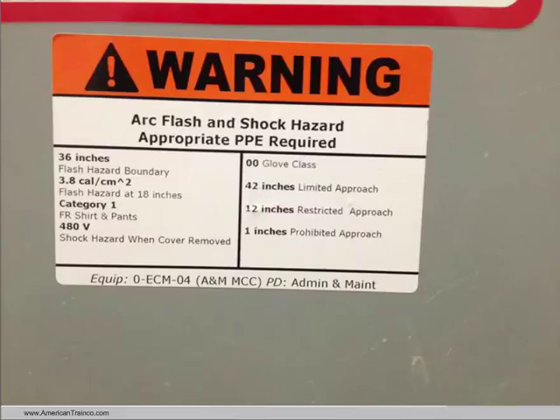So let me give you an example of where that might be a little bit of a conflict. We do the incident energy analysis method. Great. We put on the label the number of calories. Let's say it's 8.3 calories. Okay, I can go out and buy a long sleeve arc-rated shirt that would take care of 8.3 calories. It could be rated at 10.1 calories. Same with my long pants. I could get 10.1 calorie rated pants. But when that label says 8.3 calories, if I used the table method, and if we put category 3 on there, which would be the equivalent table method, my shirt and pants don't cut it anymore. I have to have a full-blown flash suit on, which is a direct conflict between having the calories on there and the clothing I have to wear to protect myself. So they have told us, you pick one or the other, don't mix and match, and that is the method that you are going to use.